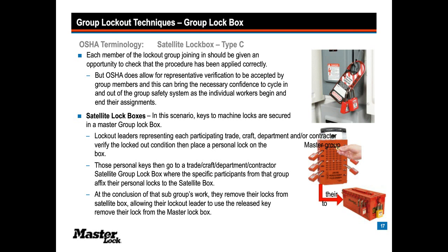They go back to the master box and they remove their representative team lock off that master box. And when all work crews complete their work, all locks will have been removed from the master box. The lockout leader then removes their lock from the box, and the machine locks' keys can then be released and the machine restored to energy.